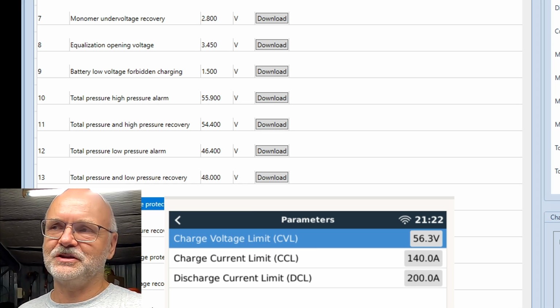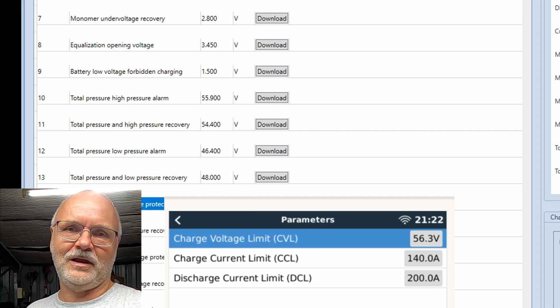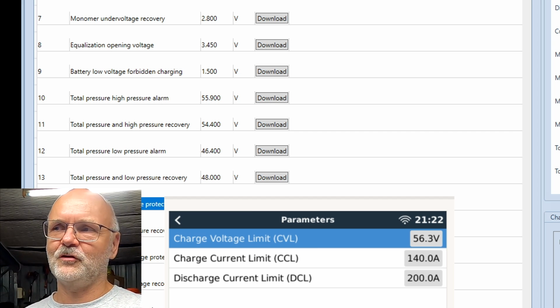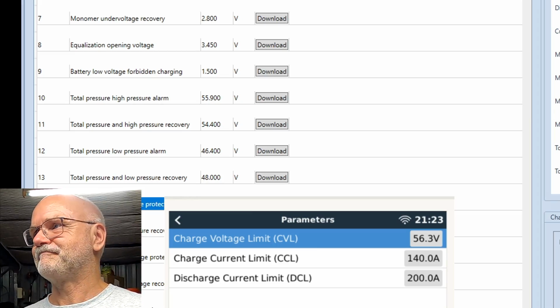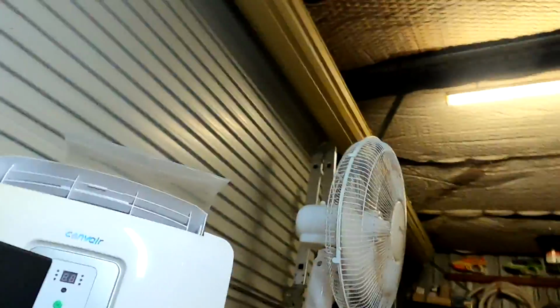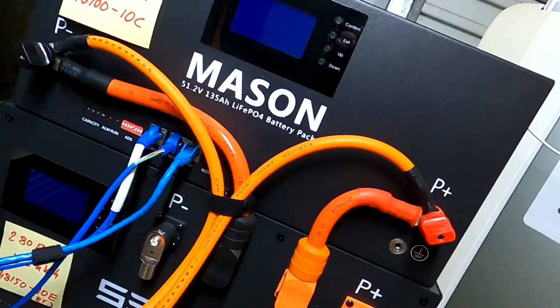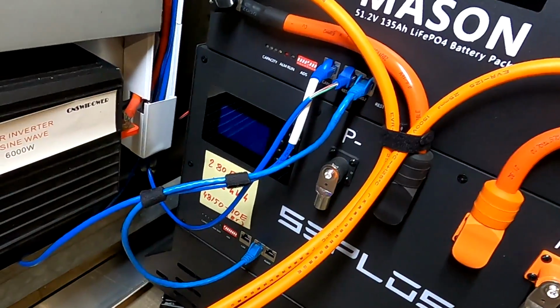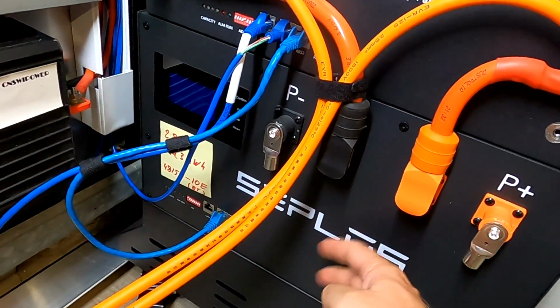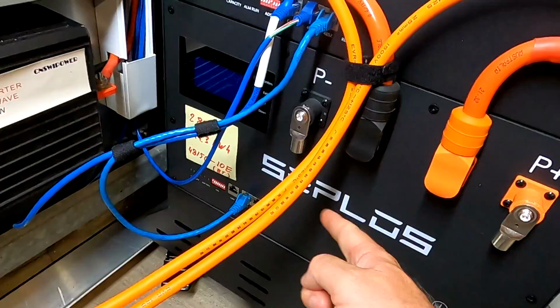We now have the limitation again. Well, I cannot show you this at all because I cannot connect to the master BMS anymore via the software. Remember that we cannot connect to the master BMS via the software when we have several batteries in parallel. That was the limitation, and SEPLOS actually recommended using the 10E as a master BMS because we can use Bluetooth to connect to it. But it's not possible with this BMS, so I cannot show you the parameters, how they change when we have 2 batteries in parallel.